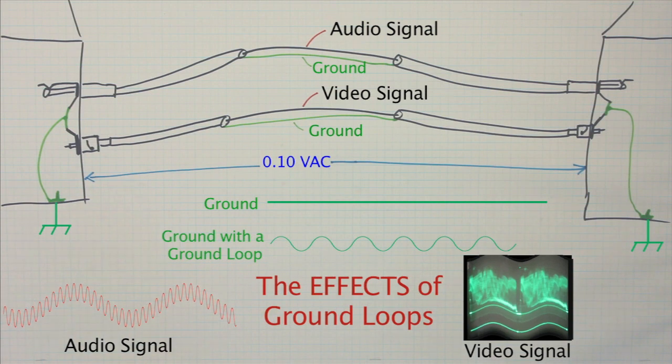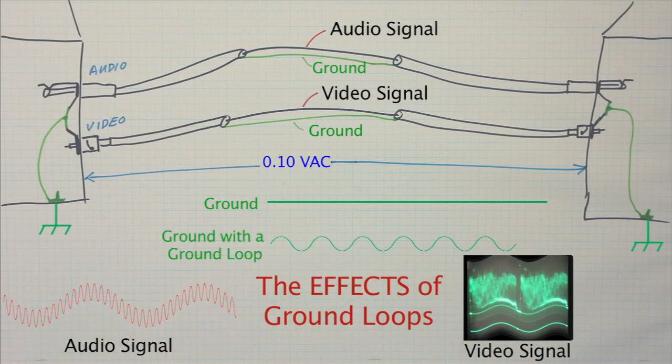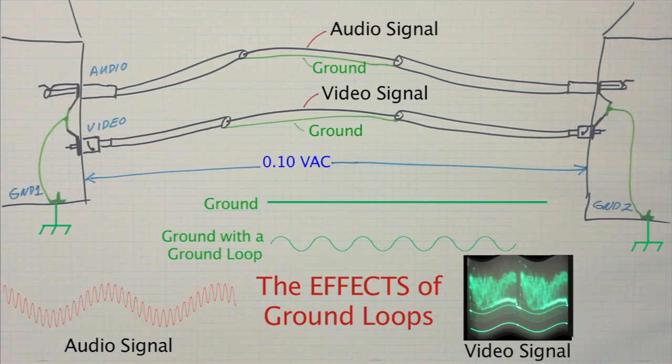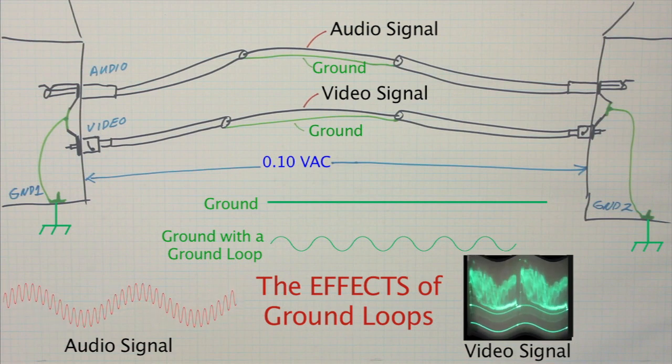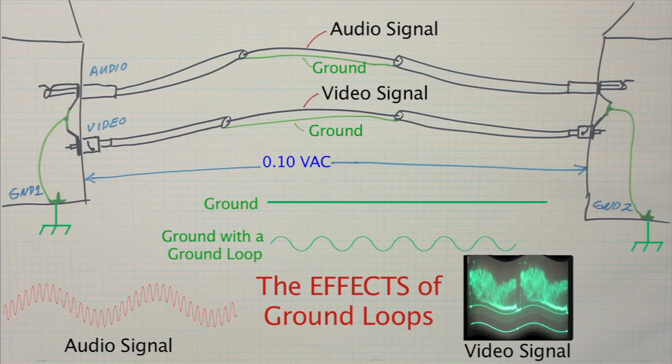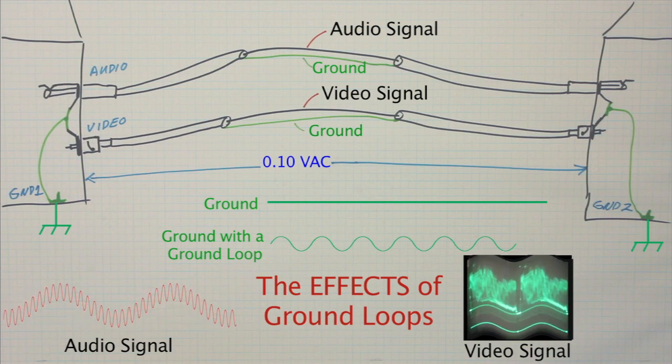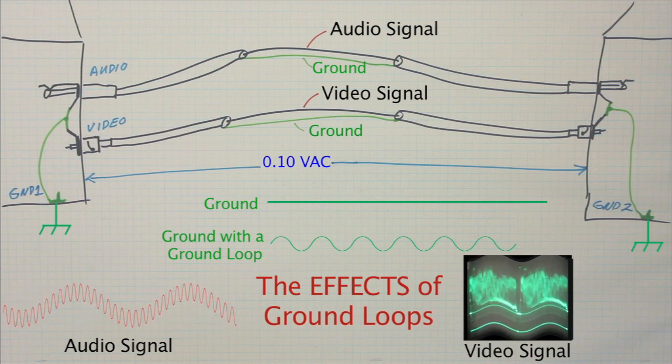With the signal ground varying in voltage, the receiving equipment sees both the intended signal and the varying signal on the ground conductor. This is why you see and or hear a 60 cycle hum and know that you have a ground loop.